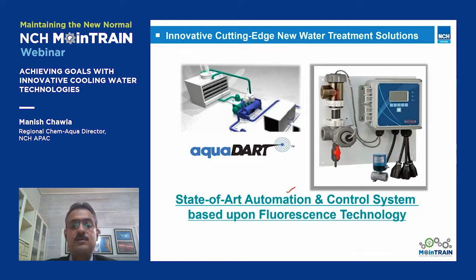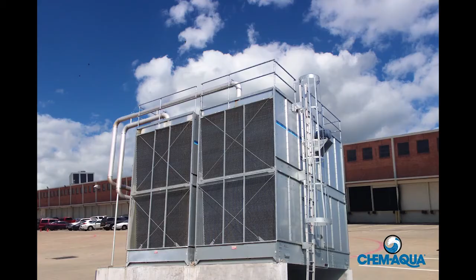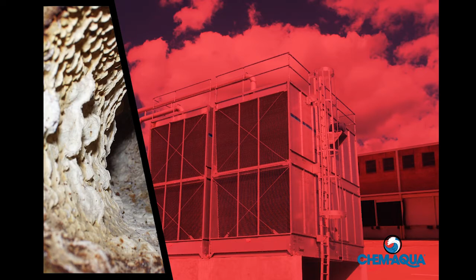Aquadart is basically, like I said, an automation and control system, and it is based on fluorescent technology. What does it do? Without proper control, cooling tower systems experience a variety of problems. Scale reduces heat transfer efficiency and can lead to system downtime. Corrosion shortens equipment life and may result in unexpected failures. Microbiological growth reduces heat transfer, increases corrosion, and can lead to pathogenic hazards such as Legionella bacteria. Inefficient water use means paying for increased water demand and wastewater generation.